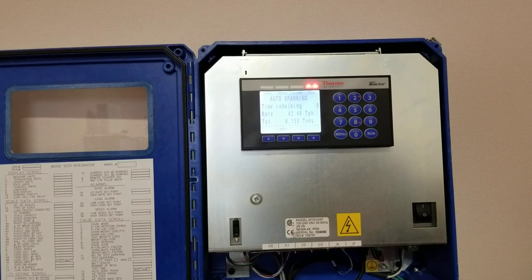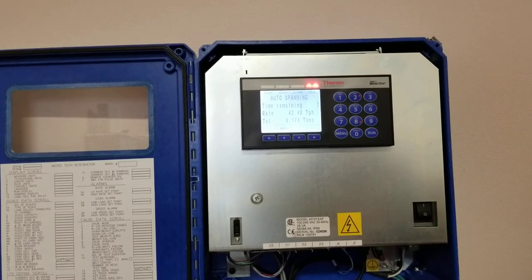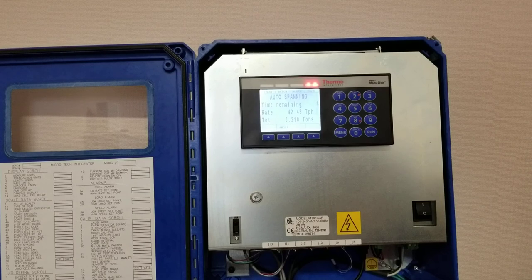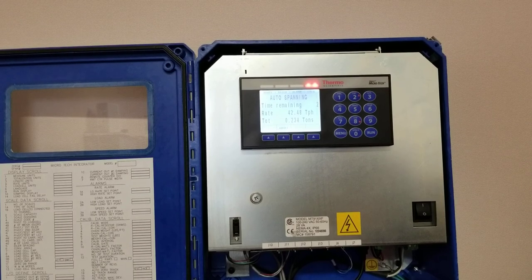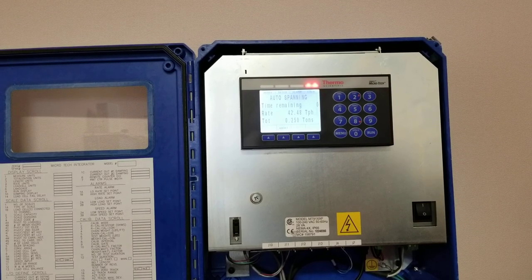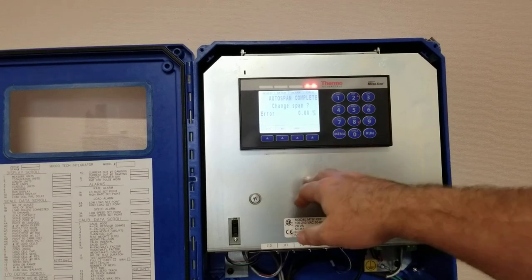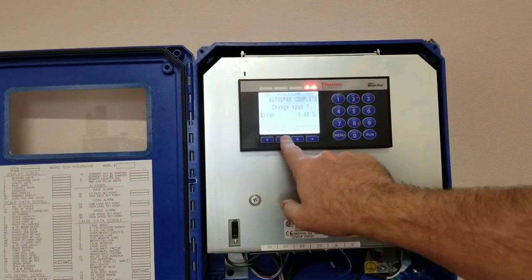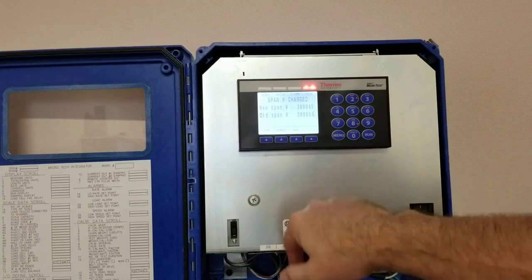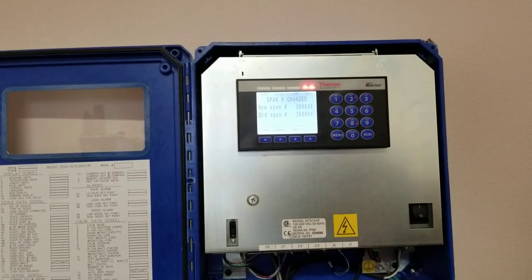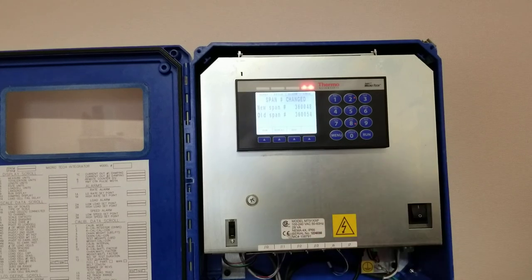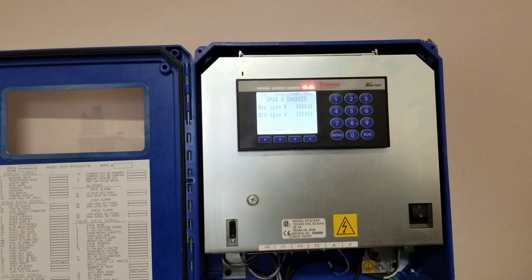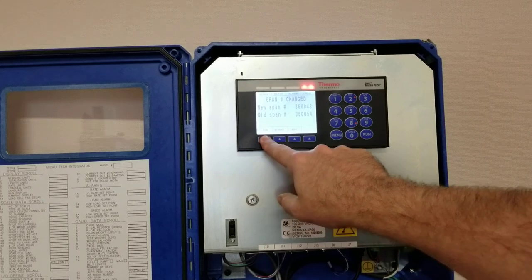And so this of course is one with the weight applied. It's going to show you tons per hour on the screen because we're employing a weight. Once it times out, then it'll come up with an anticipated error. In this case you can either say no to accepting it or yes. I'm going to say yes. When you do that you now have an A to D value for span that's on the screen, and again you should always record that value.